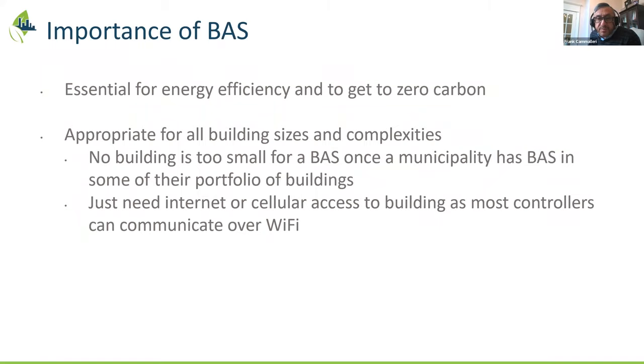Again, a fairly small place with maybe just 6-7 points, and it's becoming more and more economically attractive. Closer to 10 years ago, the general rule of thumb was 10,000 square feet as the border, where anything below that, maybe a BAS wasn't cost effective. It was just too expensive, but that has evolved and changed a lot. I wanted to stress that.